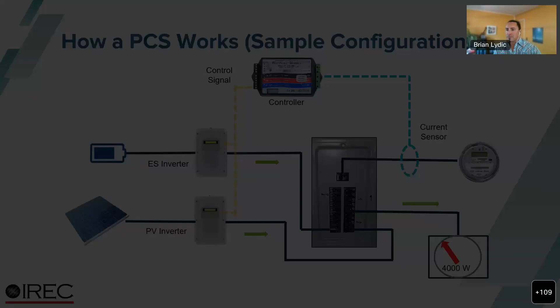The certification requirement decision, as it's called, for power control systems was published in 2019. A certification requirements decision is kind of like a fast testing protocol that can be produced by UL that doesn't go through the entire standards process like everything else in 1741 does. It's usually used for requirements that are needed on the market when you need a test standard but something doesn't exist — they can release a CRD fairly quickly, and those requirements typically then go through the full, much slower process to get incorporated into the standard itself. So this is kind of a standalone document, and they produce other CRDs.